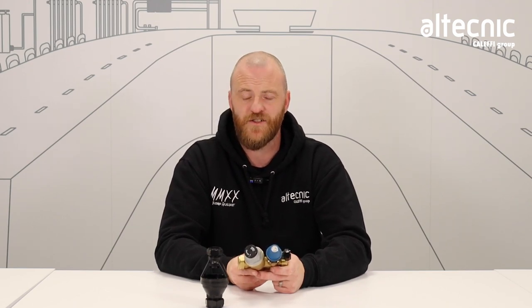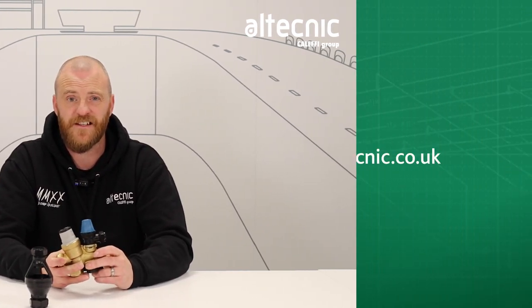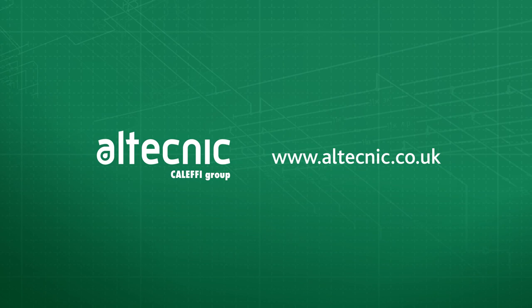Quite commonly, we get a call to say I've replaced the valve and two weeks later it's discharging again. Now that's usually down to the expansion vessel pressure not having been checked during that maintenance. So it's really key to make sure that pressure is checked. For any other business, please contact Altecnic and we'll help you. Thank you.